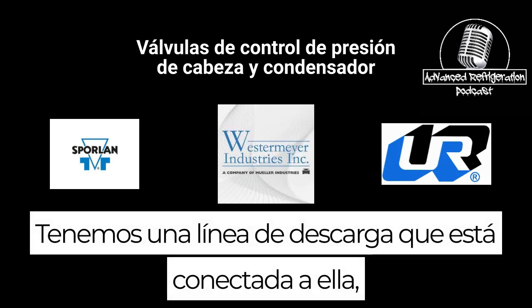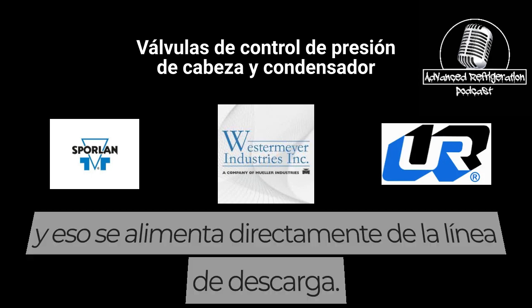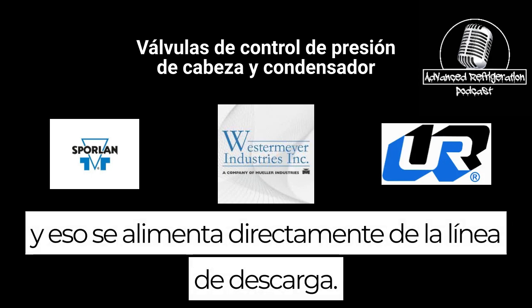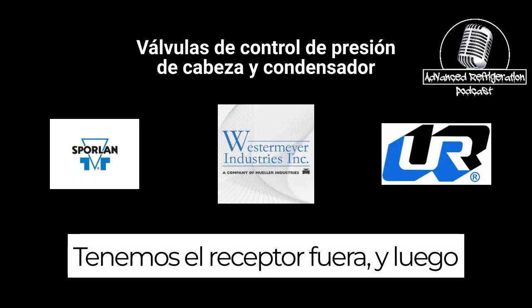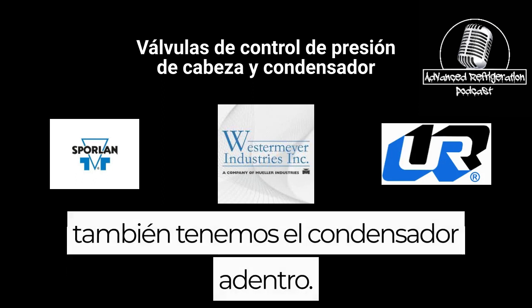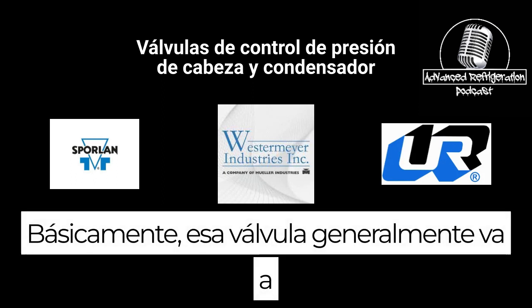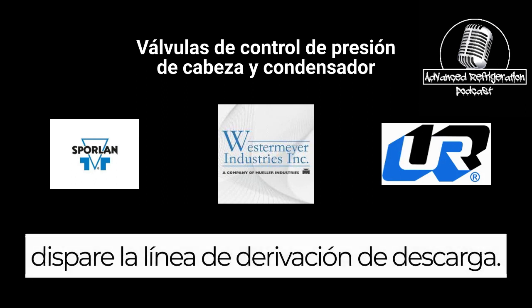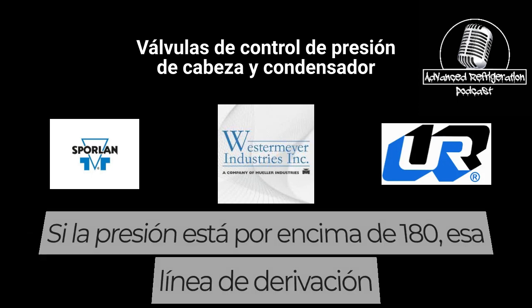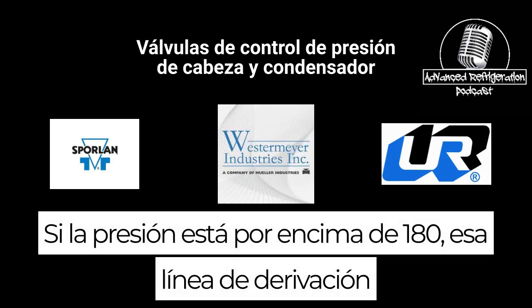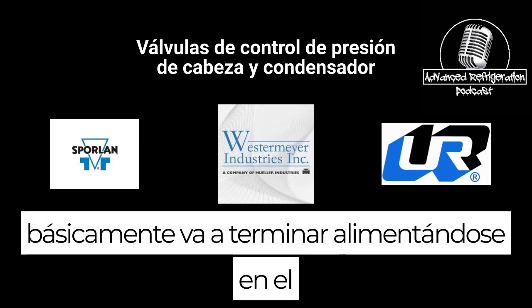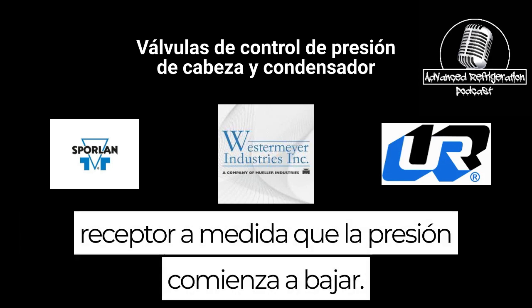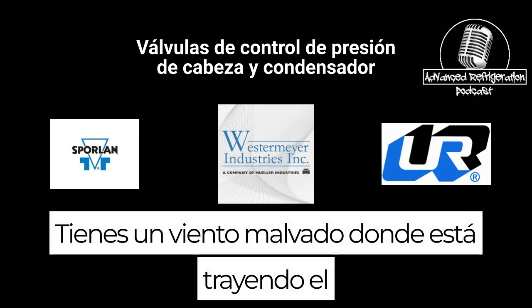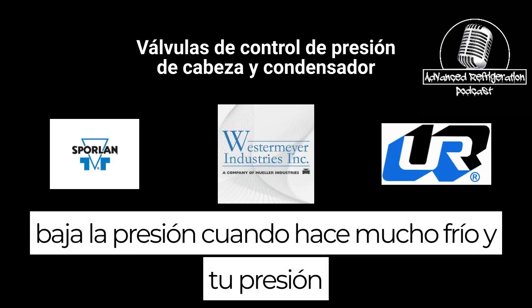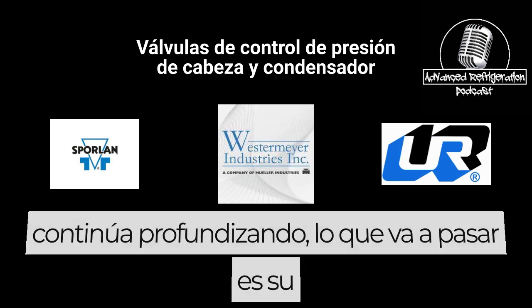We have a discharge gas line that's connected to it, getting fed right off the discharge line. We have the receiver out, and then we also have the condenser in. Basically, that valve is typically going to have the discharge bypass line shut if the pressure is above 180. That bypass line is going to end up feeding into the receiver. As the pressure starts to go down, you have either a wicked wind bringing the pressure down when it's really, really cold out, and your pressure continues to dive down.